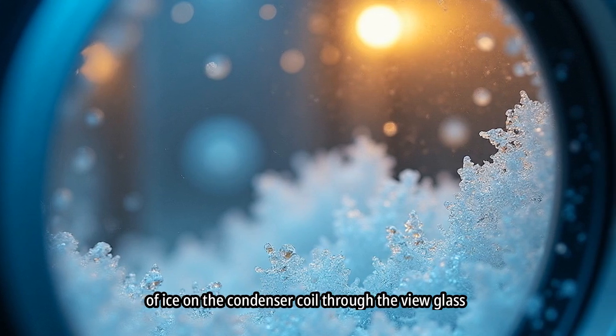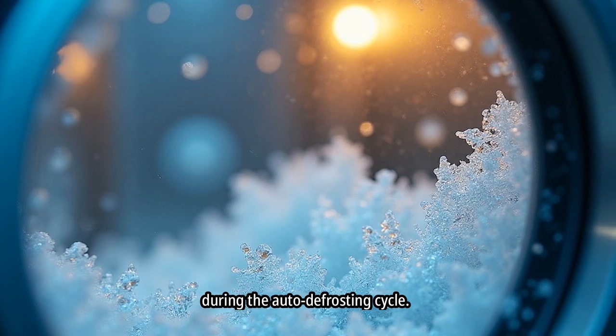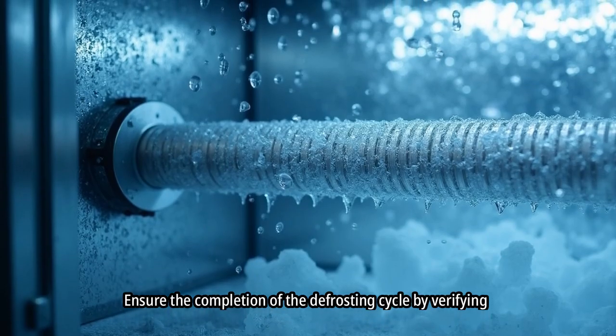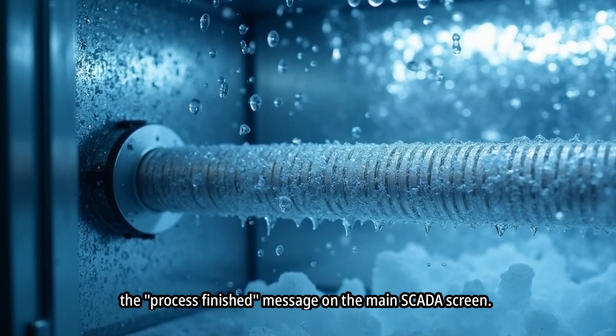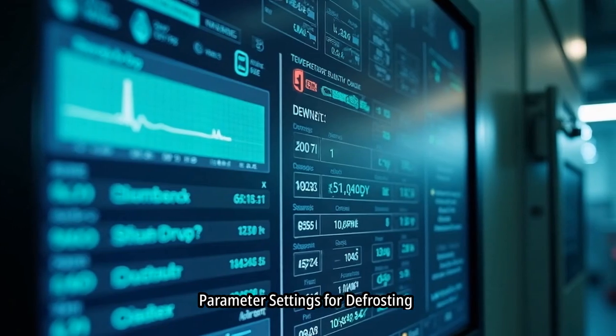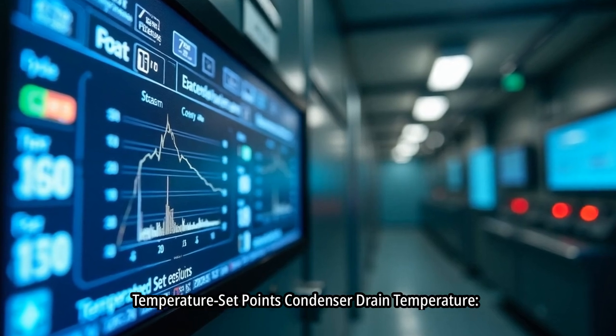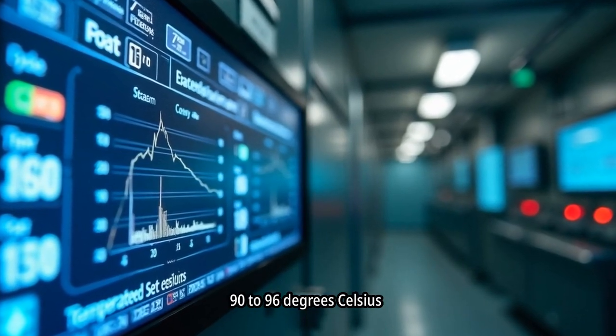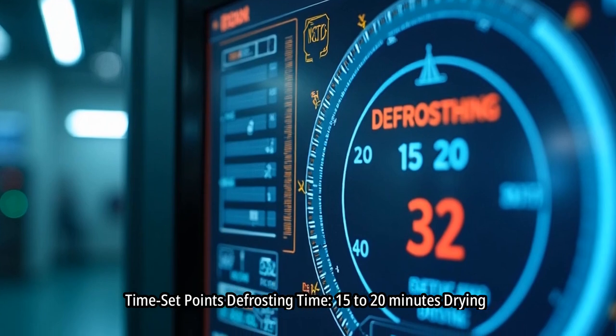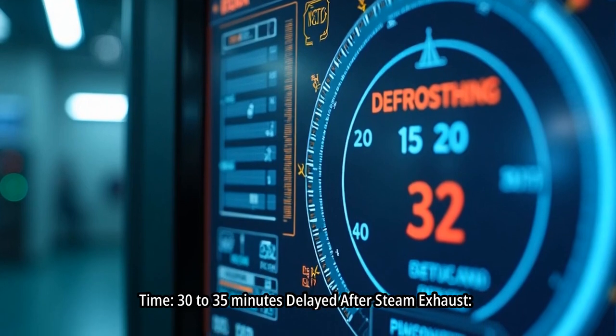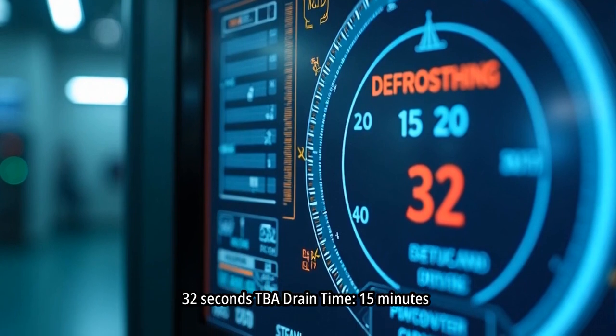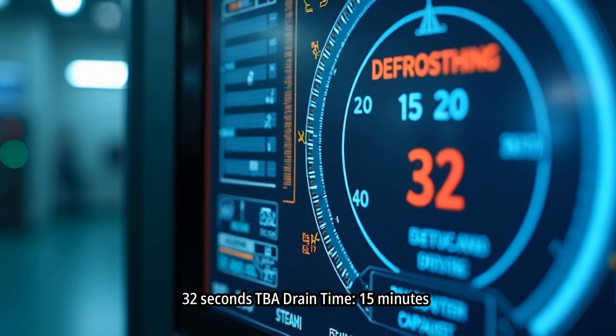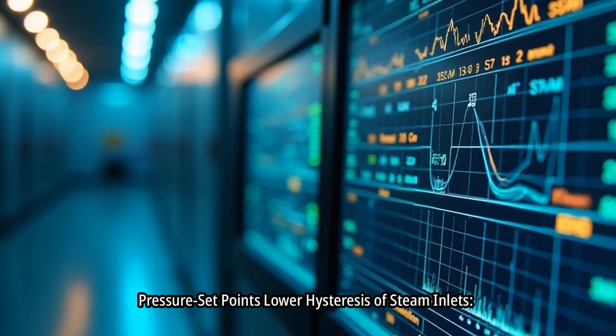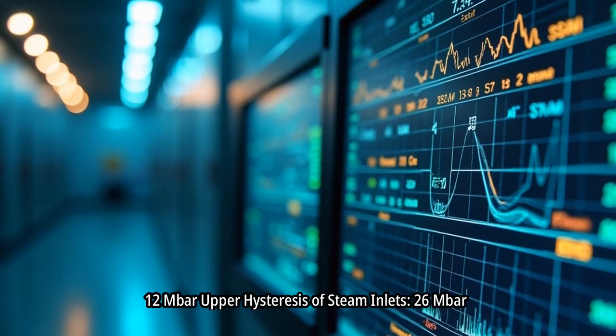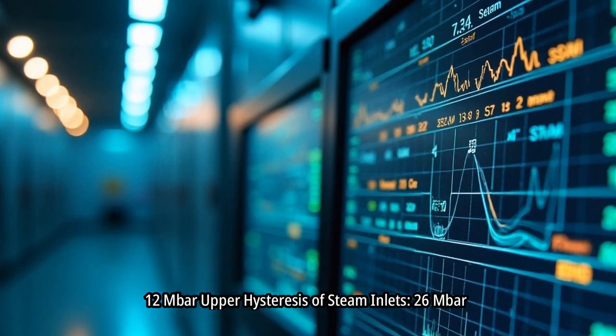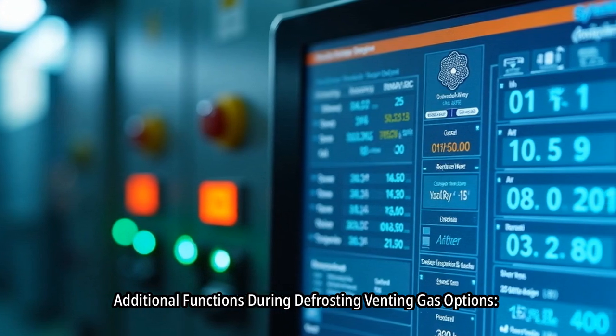Monitoring and completion. Visually check the presence of ice on the condenser coil through the view glass during the auto defrosting cycle. Ensure the completion of the defrosting cycle by verifying the process finished message on the main SCADA screen. Parameter settings for defrosting. Temperature set points: condenser drain temperature, 90 to 96 degrees Celsius. Time set points: defrosting time, 15 to 20 minutes; drying time, 30 to 35 minutes; delay after steam exhaust, 32 seconds; TBA drain time, 15 minutes. Pressure set points: lower hysteresis of steam inlets, 12 mbar; upper hysteresis of steam inlets, 26 mbar.